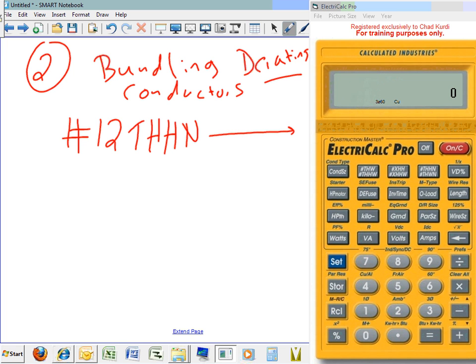And if you guys take this one to 310.15B16, 310.15B and a 16 under the 90-degree column. Anybody can tell me why the 90-degree column? We're derating, and it's THHN. How much current can I get out of number 12 THHN under the 90-degree column? Why did I go to the 90-degree column, guys? Because it's derating.